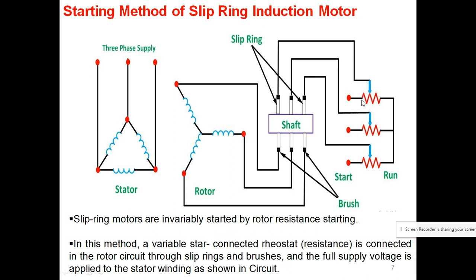You see there are three variable resistances here. In this method we use a variable star connected rheostat; rheostats 1, 2 and 3 are connected to the rotor circuit. The whole of this is our rotor circuit: the shaft, the slip rings and this structure are all known as the rotor circuit here. These three rheostats are connected in series with the rotor circuit with the help of the slip rings and brushes. And the full supply voltage is applied to the stator winding. This is our stator winding, and we give our three phase input supply here, here and here, and this is the rotor, and this is the air gap. We know how the induction motor works, so the same principle works here. So what will happen here?